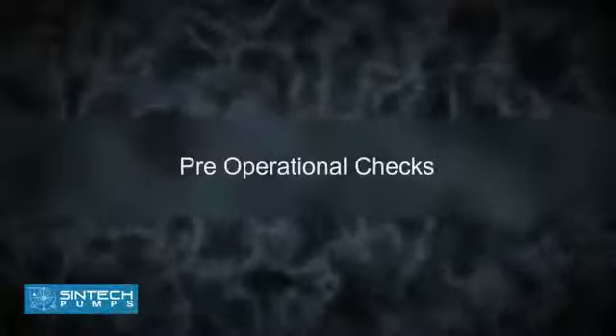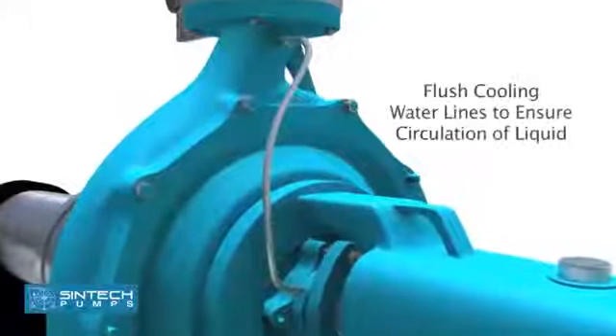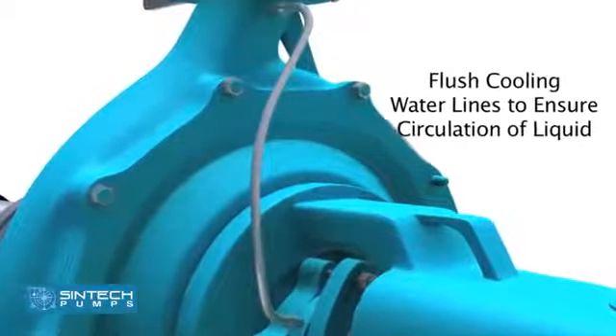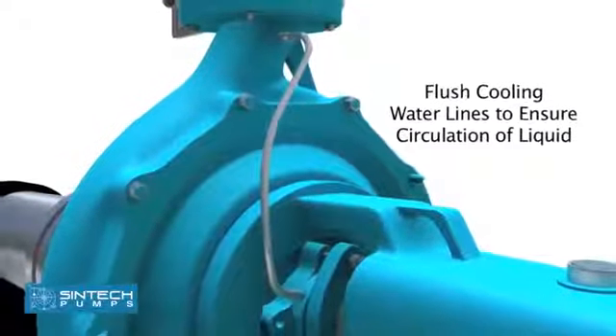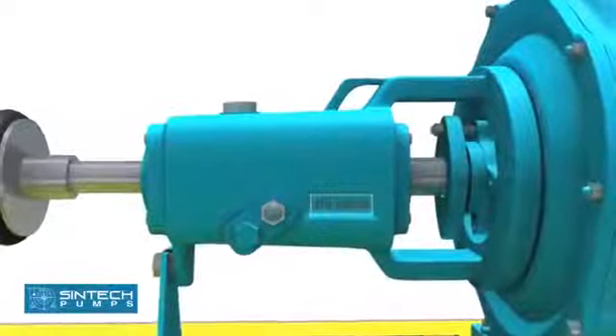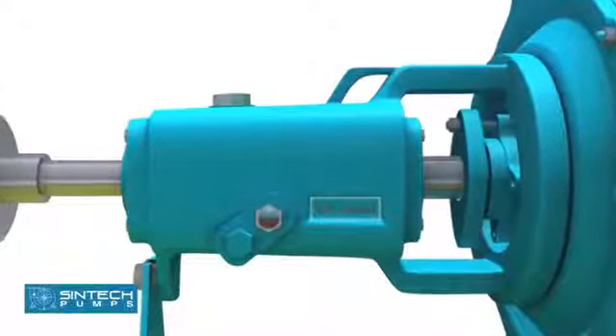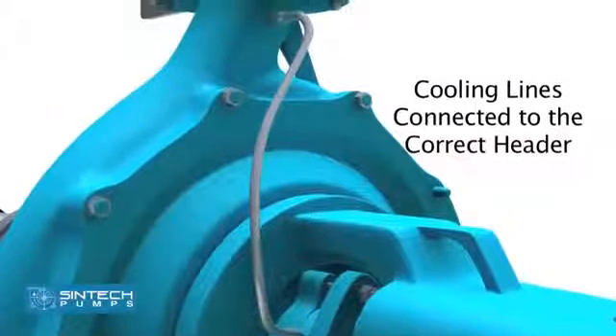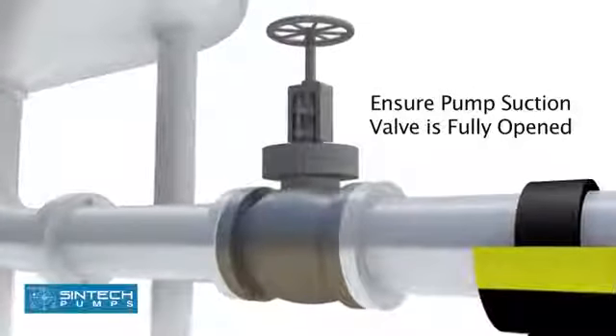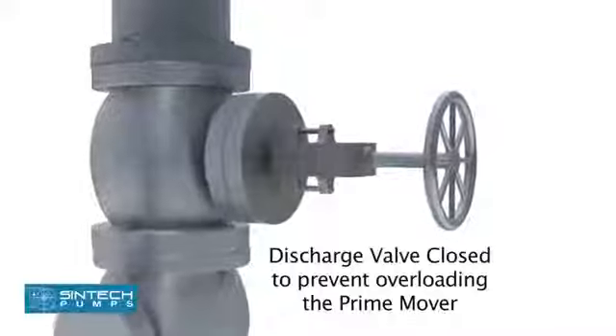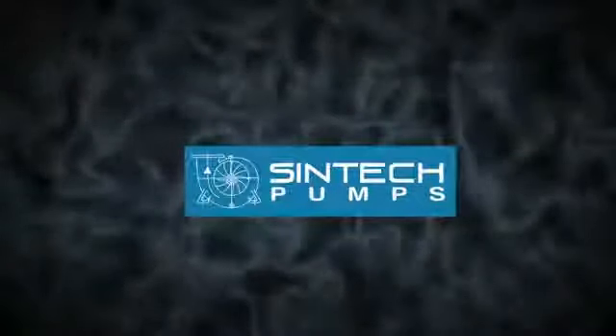Pre-operational checks: All cooling water lines connected to the pump need to be flushed. The cooling water lines are opened and circulation of liquid is ensured. Bearing housing should be drained of their oil and refilled with fresh oil of correct viscosity. It is necessary to confirm that the supply and return cooling lines are connected to their correct header. Place the coupling guard and tighten the bolts. Ensure that pump suction valve is fully opened and all joints are checked for any leakage. The opening of discharge valve is kept closed as this prevents overloading the prime mover.